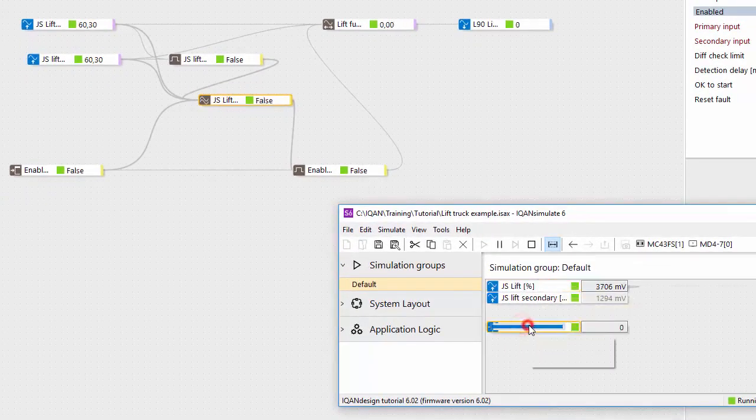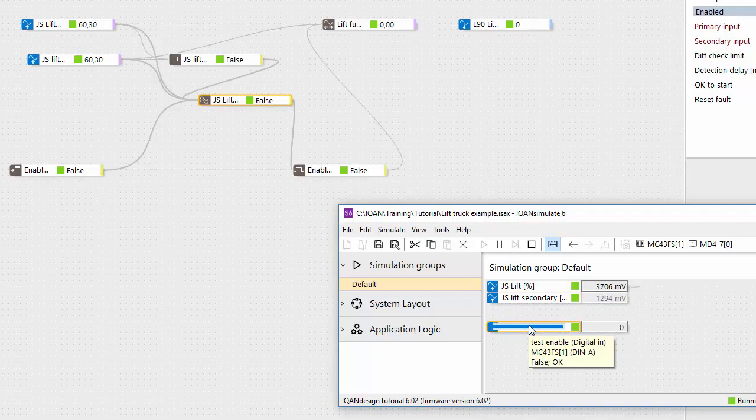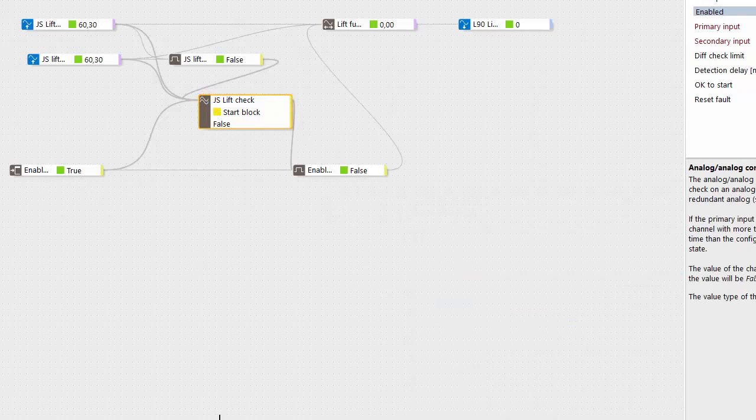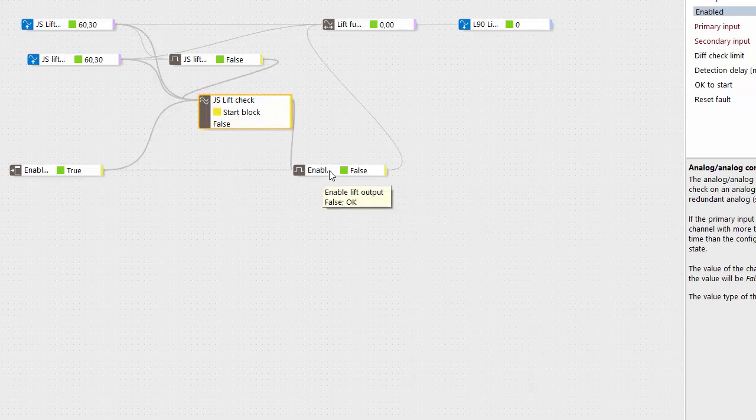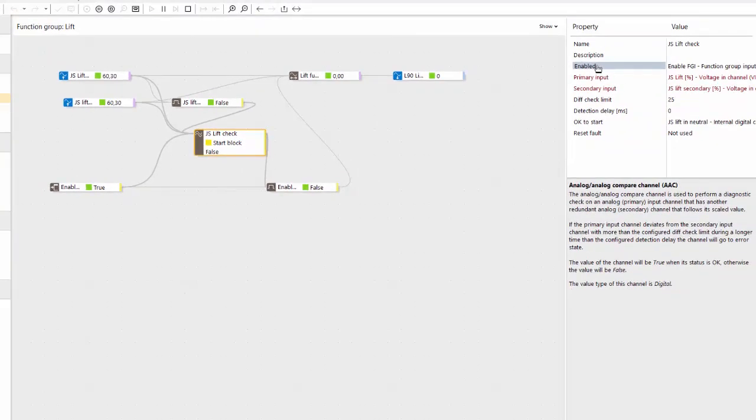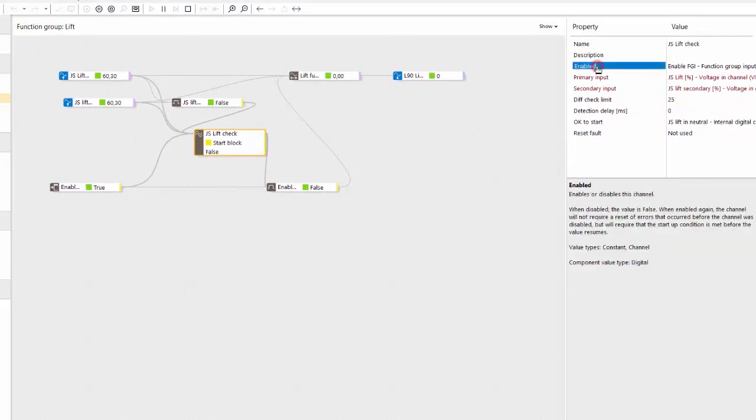And then we can activate. If we disable and enable again we're back in this start block. So that way we can combine the compare channel with another safety function using this enable property.